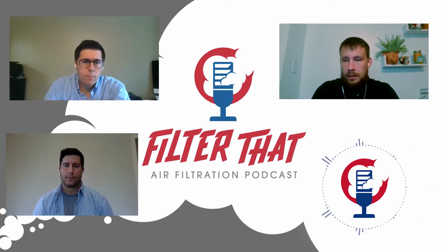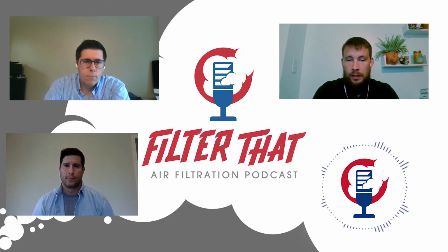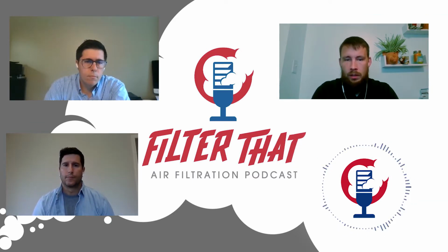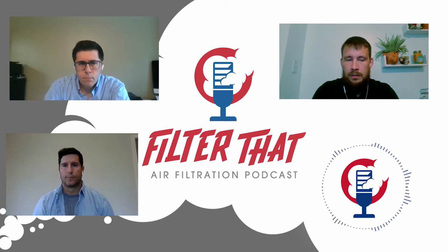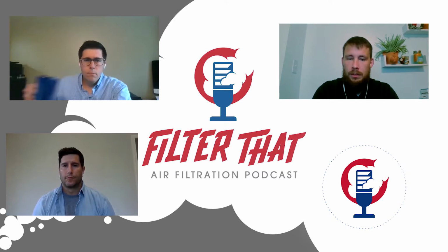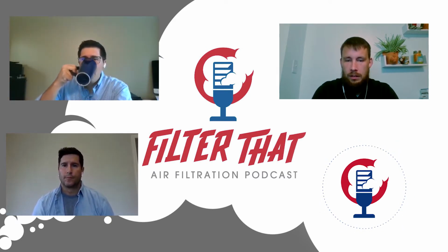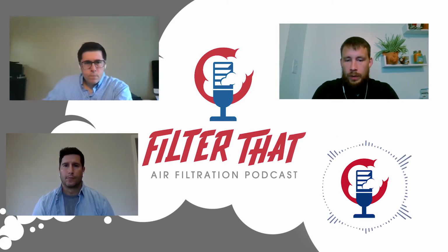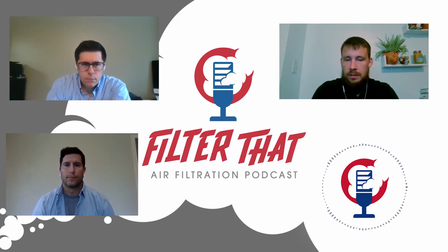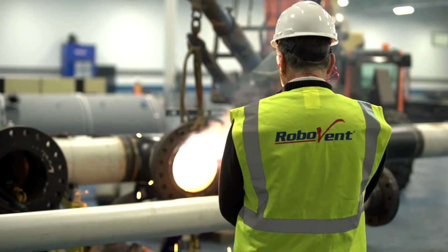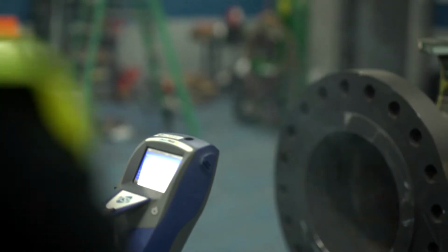We started mainly trying to do everything. We found out very quickly that oil mist is one thing we cannot do with our CFD capabilities. It's too hard to find the generation rate from the oil mist. A lot of it gets recycled, so people don't quite comprehend what they're using on a daily basis. And the CFD software doesn't actually mix moisture and gas very easily. So oil mist CFD simulations, that's something we can't do effectively. Everything else is pretty much on the table.